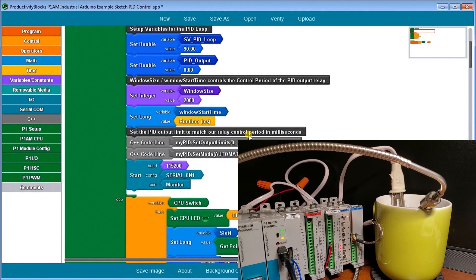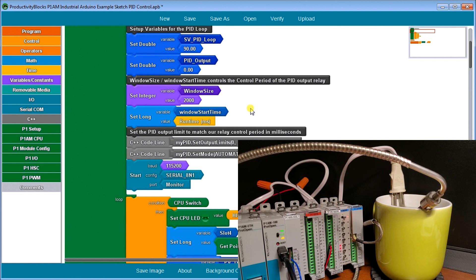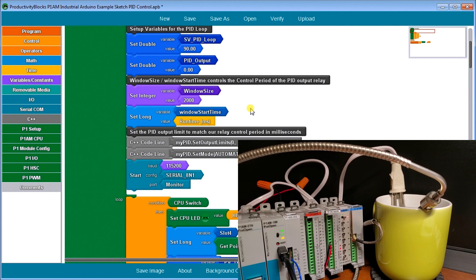Then what we're going to do is we're going to set the control period for our relay output. And that it's going to be called window size, which is going to be 2000 milliseconds. So two seconds. So what's going to happen is we're going to take a look at that output that we have to monitor of our PID loop. And it's going to split that 2000 milliseconds up to a portion of that to turn the relay on. And that's how we do proportional control on the relay itself.